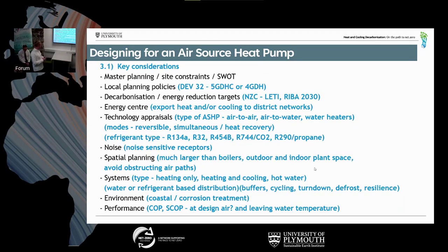Spatial planning - this is an important consideration with most heat pumps, but particularly air source. They have a footprint, they need to go outside, and they can be a lot larger than boilers, and that's the main issue. They need an indoor plant space as well, because you've got all of the equipment that needs to support that heat pump. And just a quick one - don't obstruct the air paths. They need to be in a space where they're not obstructed by walls, fences, all that type of thing, just so that they can take the heat from the air effectively, or you'll just create a little heat island, if you will.